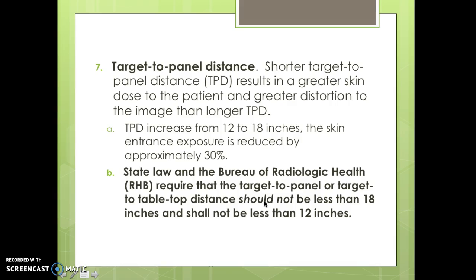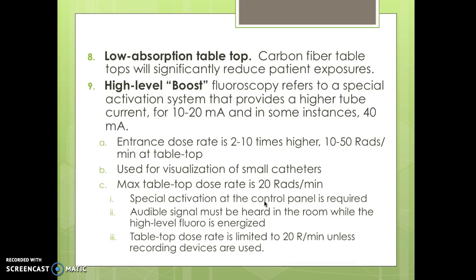Target to panel distance: a shorter target to panel distance results in greater skin dose to the patient and greater image distortion. Increasing the TPD from 12 to 18 inches reduces skin entrance exposure by approximately 30 percent. State law and the Bureau of Radiologic Health require that the target to panel or target to table distance should not be less than 18 inches and shall not be less than 12 inches.